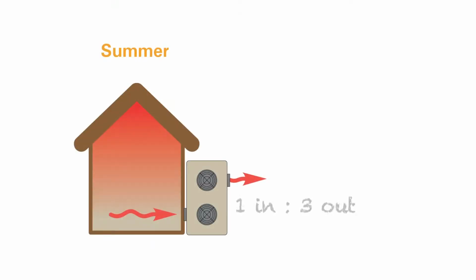It's important to note that this is 288 degrees Celsius warmer than absolute zero. And this substantial variation provides an opportunity for redistribution or movement of energy, or heat. Heat pumps are a very efficient method of moving heat from one place to another. Typically in summer, we want to move heat outdoors, and the heat pump does just that. For 1 kilowatt of energy that we put into a heat pump, it will move 3 kilowatts of energy or heat outside.